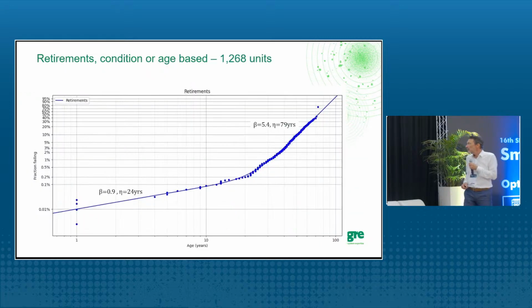Okay, now this function we used for the statistical analysis, and in this case you can see the retirements. So we checked after which year a transformer was retired, and for each case we have one of these dots. And these dots we fitted with, let's say, 2 Weibull distributions. In the first 20 years, you can see a line which corresponds to 0.9 as beta and 24 to eta. And after 20 years, beta increases to 5 and eta is 79 years.